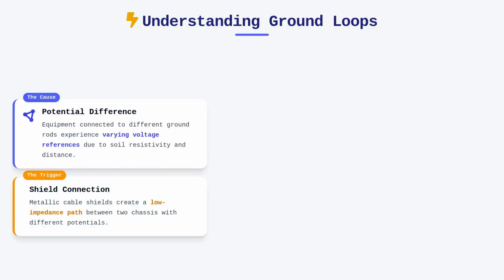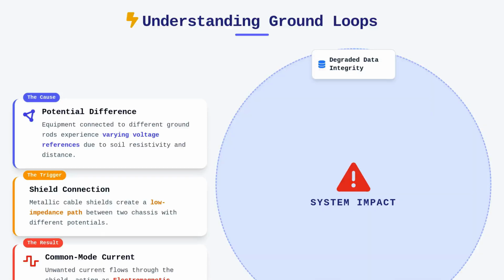When you connect two chassis using a metallic shield of a data cable, you effectively create a low impedance current path between these 2 points. Because the potential difference acts as a driving voltage, an unwanted common mode current begins to flow through the cable shield. This current is not part of the intended signal transmission and instead functions as a source of electromagnetic interference. Left unchecked, this phenomenon leads to degraded data integrity, intermittent cyclic redundancy check errors, and, in severe cases, the thermal destruction of communication transceiver components.